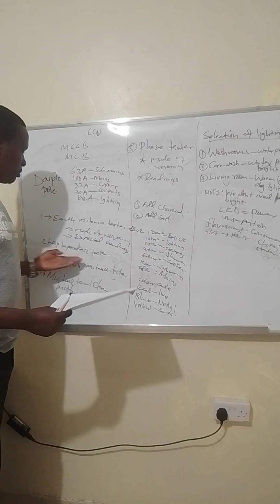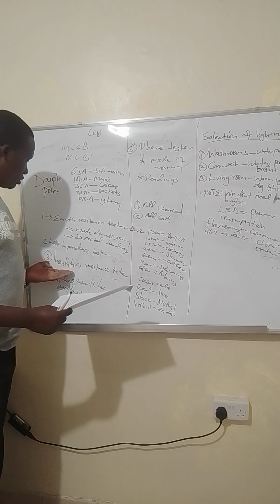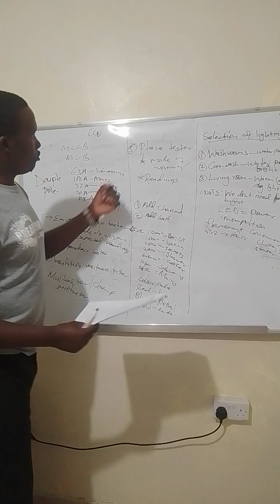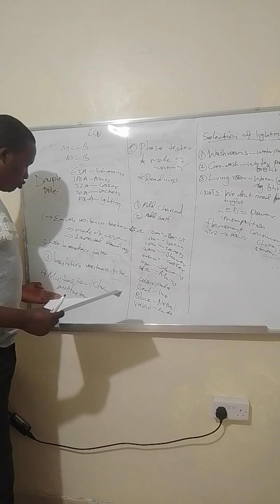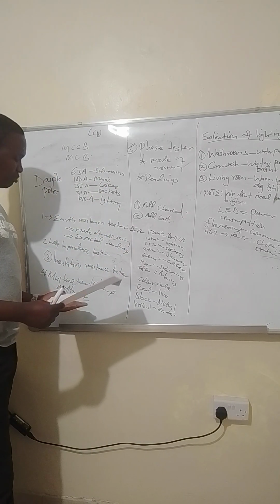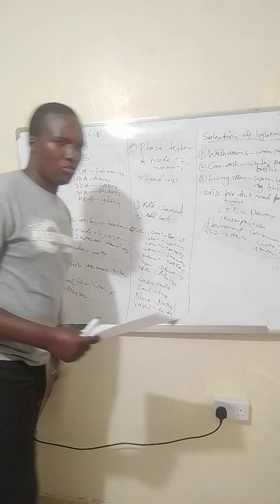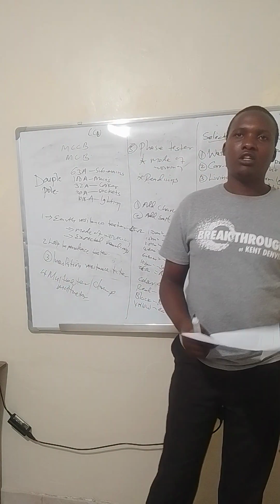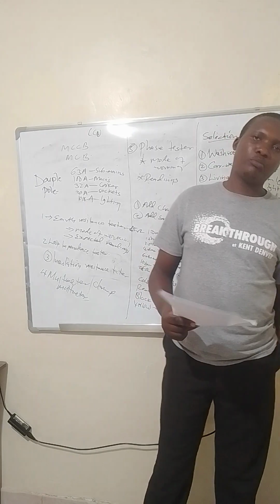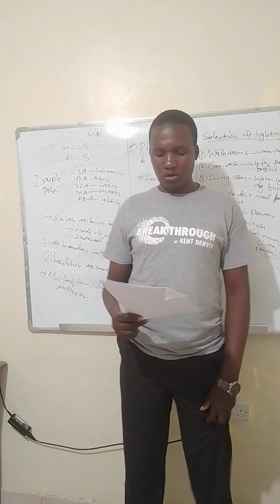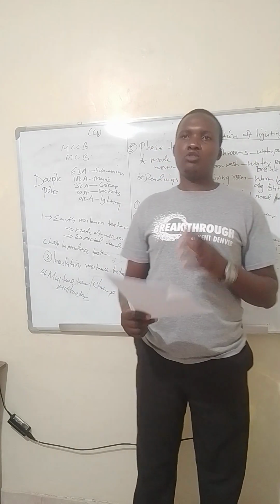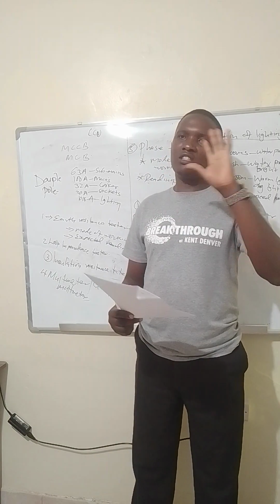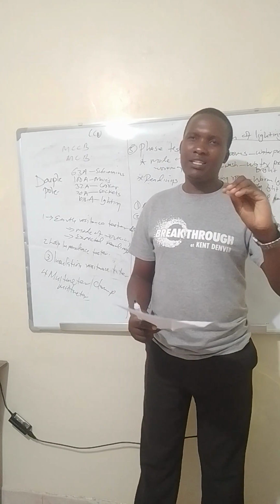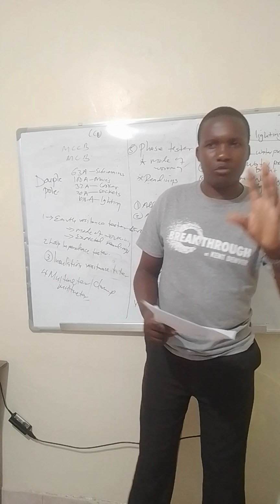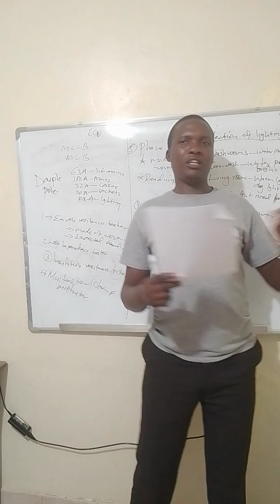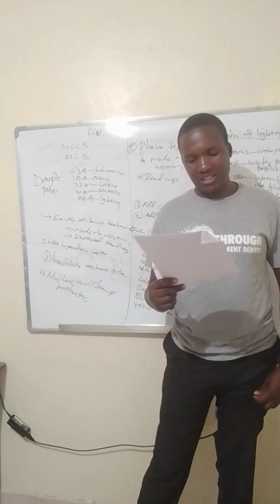You need to do a loop impedance test, an insulation resistance test, a continuity test, and a polarity test. Those are the tests you need to do before handing your project to the owner, because these tests ensure your project is secure from injuries and accidents, even death, to human beings, and to the domestic installation itself.